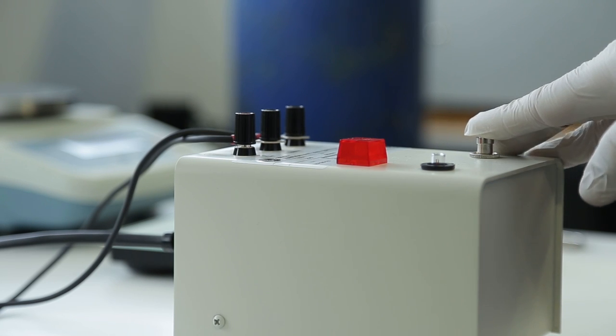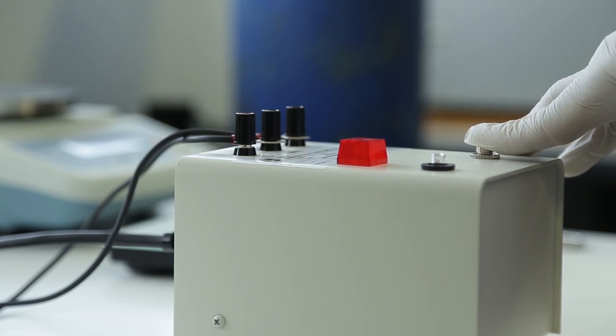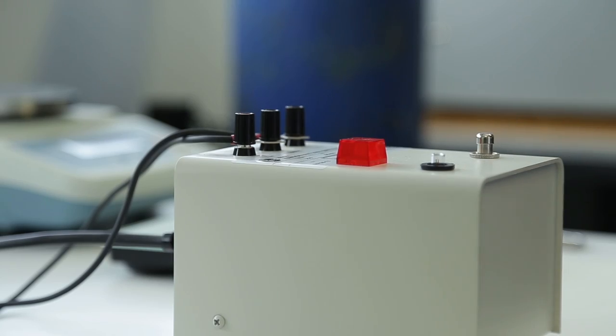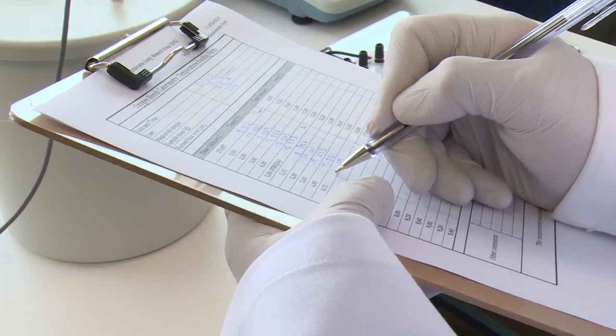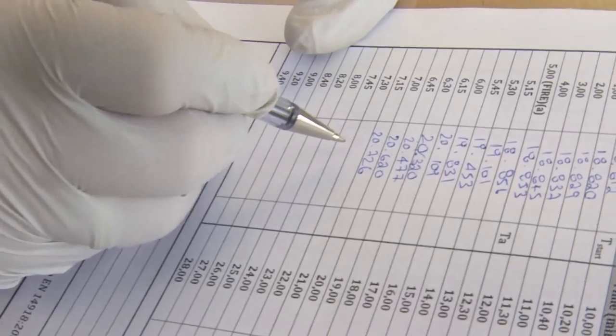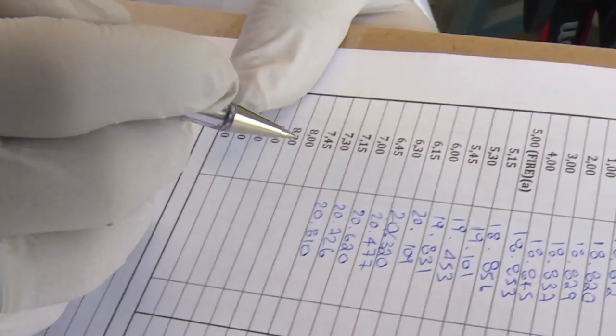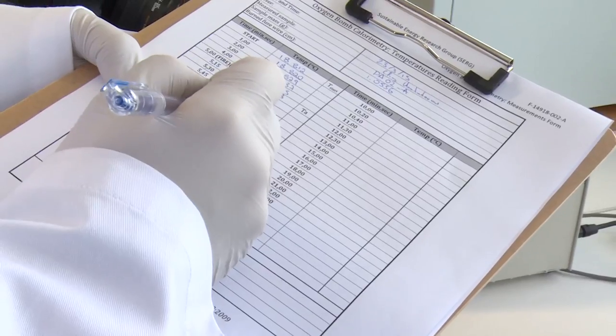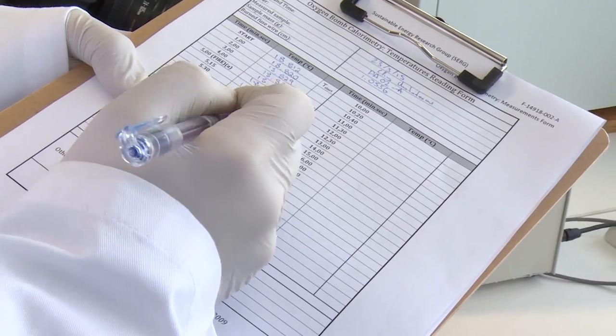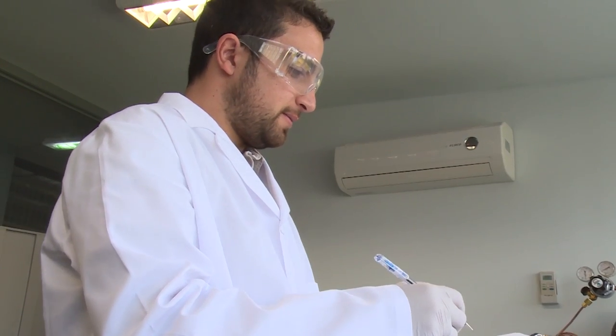stand back from the calorimeter and fire the bomb by pressing the ignition button and holding it down until the indicator light goes out. Measure the time required to reach 60% of the total rise by estimating the temperature at the 60% point and observing the time when the temperature reading reaches that point.